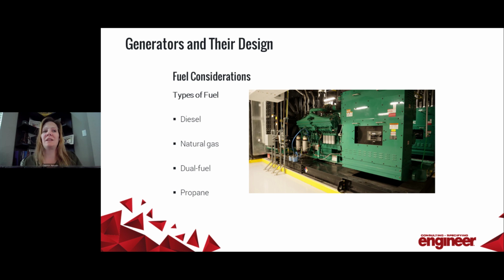They do have some disadvantages though. Diesel fuel must be treated. The fuel has a shelf life, so it has to be treated and maintained in order to maintain that ASTM #2 standard. And it's also not considered very clean burning, not nearly as much as natural gas anyways.